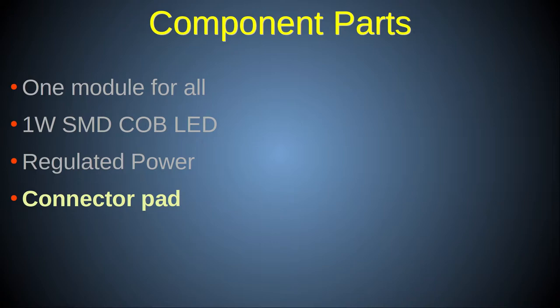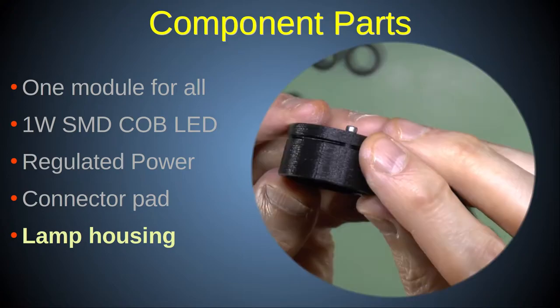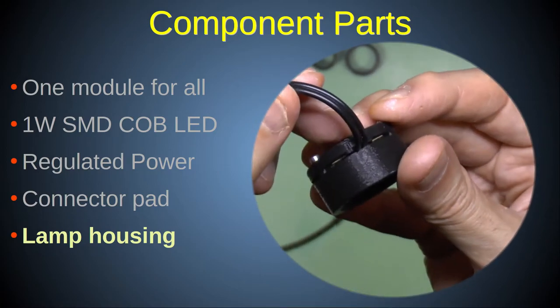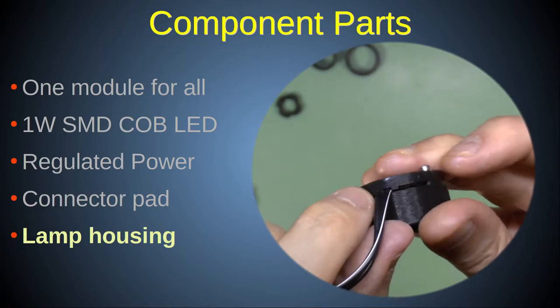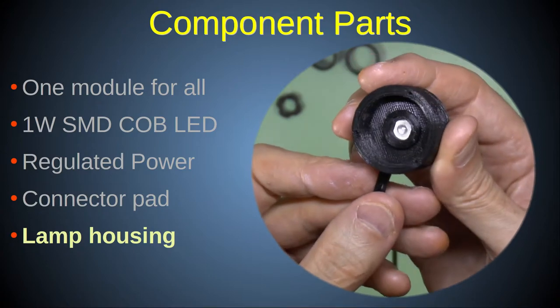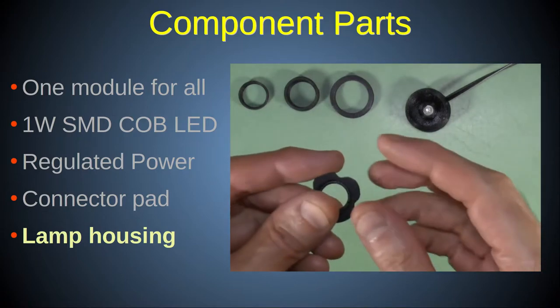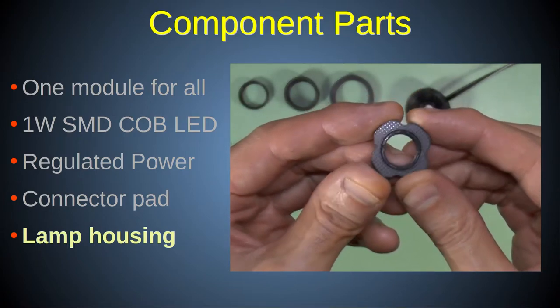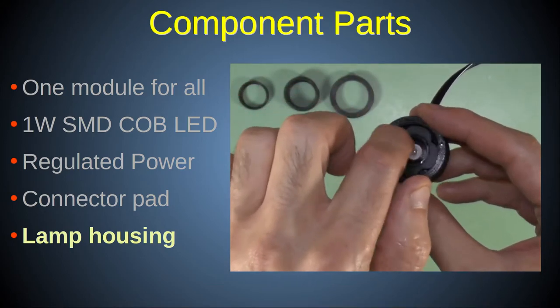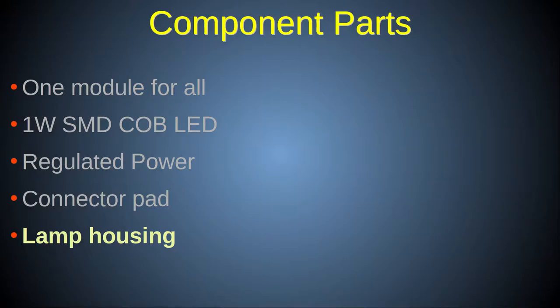In order to hold the LED bulb against the connector pad and keep everything together in a unit that can be easily coupled to the microscope, Puma specifies a 3d printed LED lamp housing and I'll show you how to construct that shortly. The lamp housing is designed to accept a spacer and various filters to allow adjustment of the light intensity, diffusion and wavelengths, as well as to adjust the spacing of the LED from the lower collector lenses to adjust the beam collimation to be optimal for different illumination modes as will be discussed later.